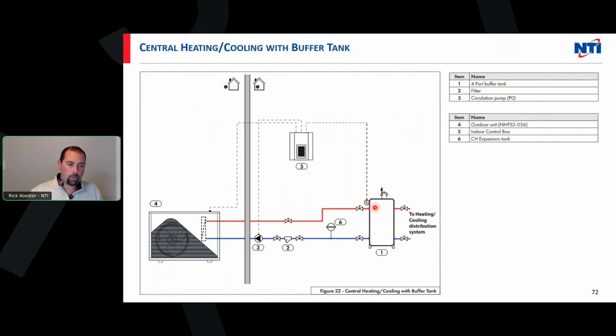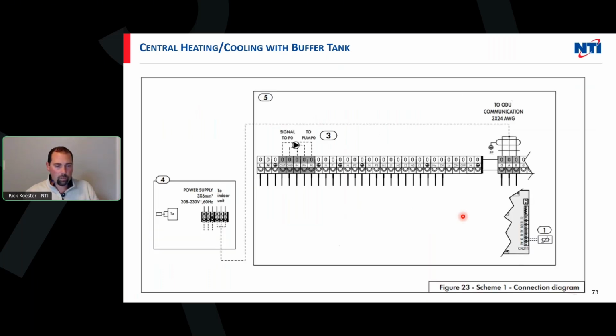We need a buffer tank sensor going back to our control box. We have a circulator output going back to the control box, and a communication cable going from indoor to outdoors, and they're all called out here. So this is just a little sample of a basic central heating and cooling system with a buffer tank. From there, we show where we land these terminals, so they can see it on the piping diagram.